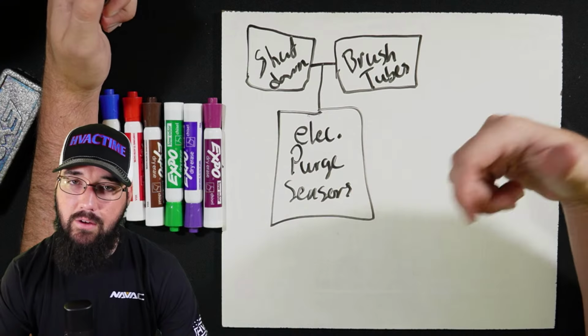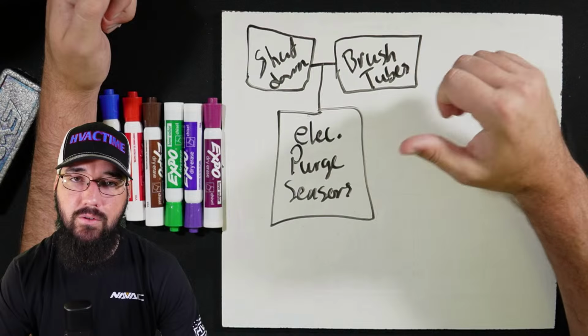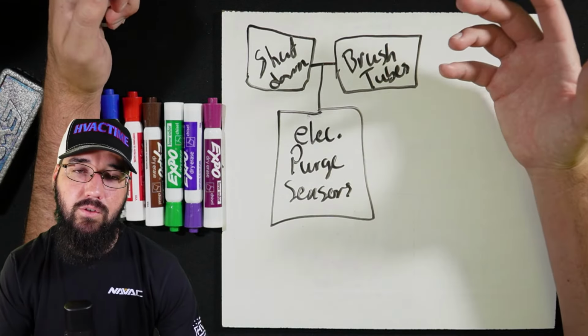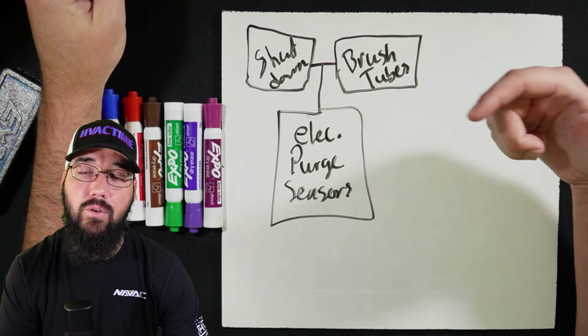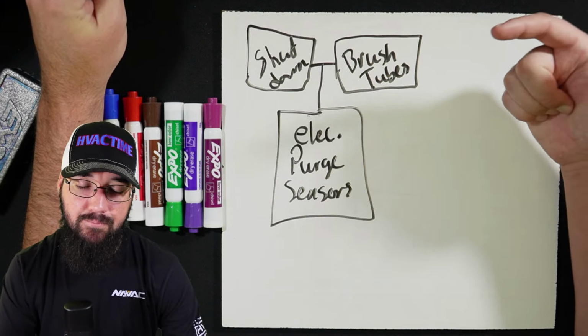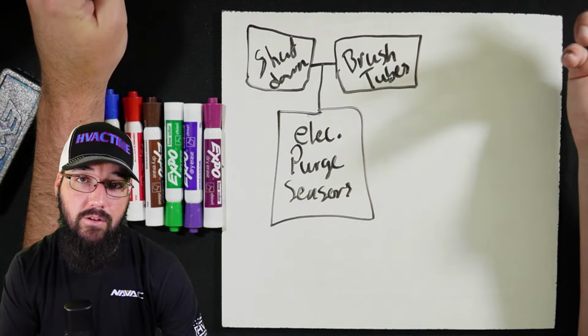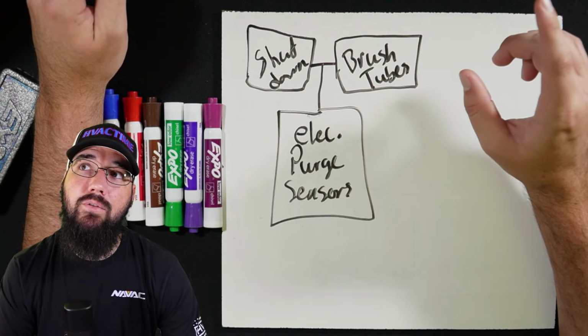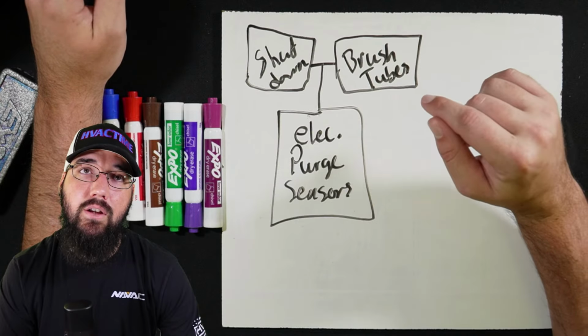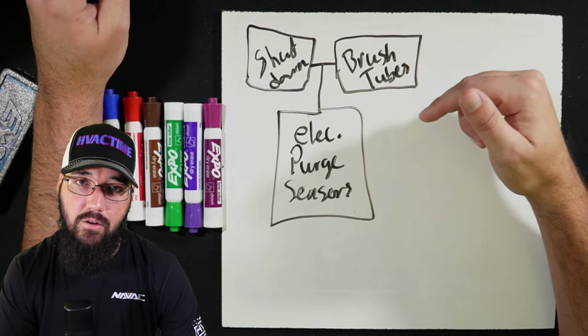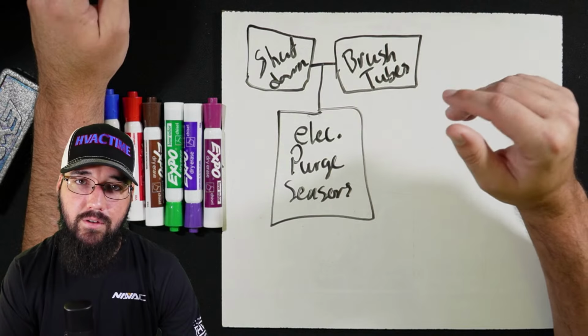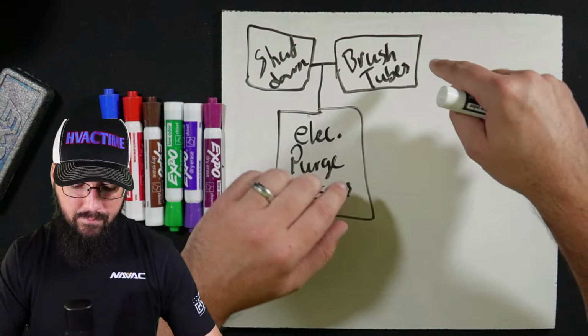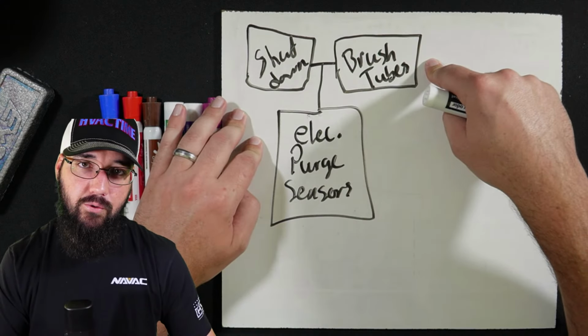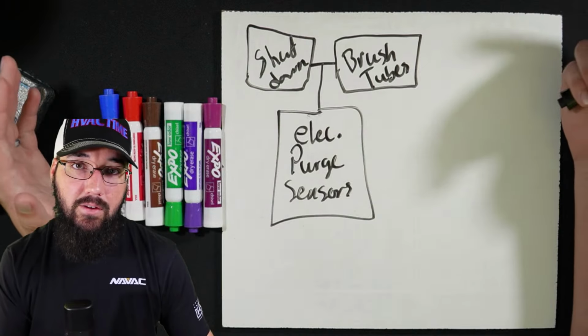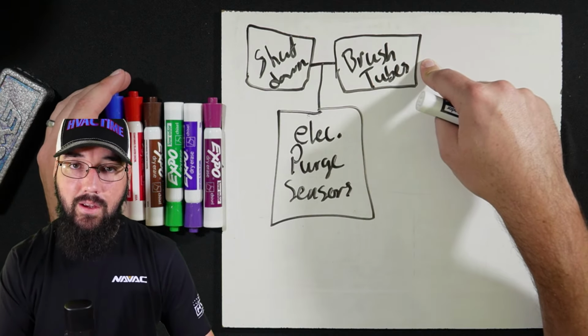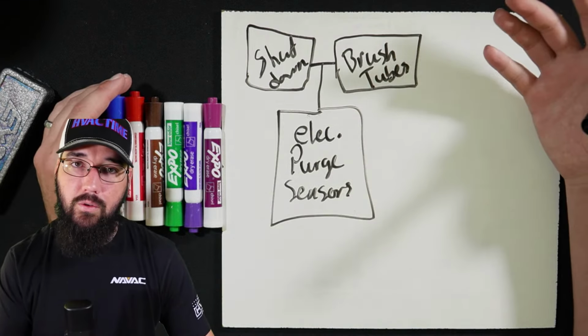And then, yeah, verifying your sensors, all your temperature sensors, your pressure sensors, which depending on your vintage of your CVH, newer machines do have a high pressure transducer. It's usually located inside of the purge cabinet. But if it's an older machine, there may not be any, well, you would still have the oil pressure transducer. You just may not have refrigerant pressure transducers on the high or low side. So that's going to depend on the vintage of your chiller. Anyway, all that is happening while this guy's brushing tubes. Depending on the size of your machine, this may take a day, this may take 3 days. So it's just a lot of work goes into brushing a machine.